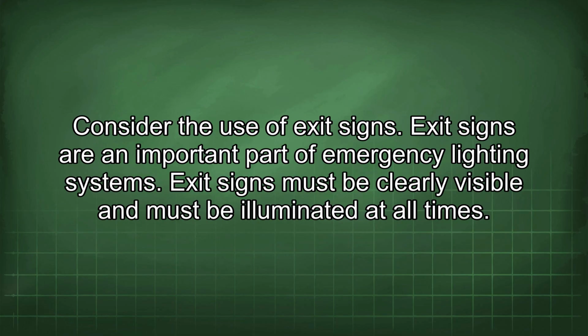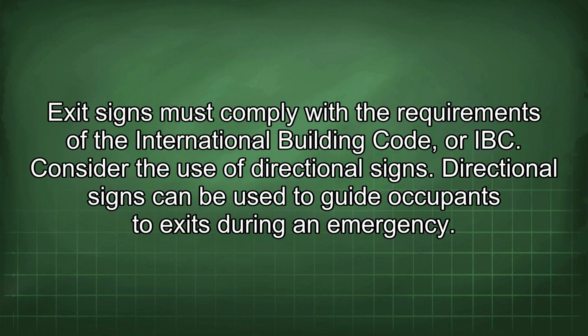Consider the use of exit signs. Exit signs are an important part of emergency lighting systems. Exit signs must be clearly visible and must be illuminated at all times. Exit signs must comply with the requirements of the International Building Code, or IBC. Consider the use of directional signs. Directional signs can be used to guide occupants to exits during an emergency.